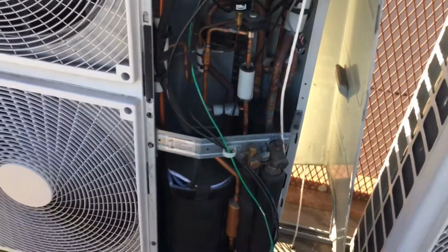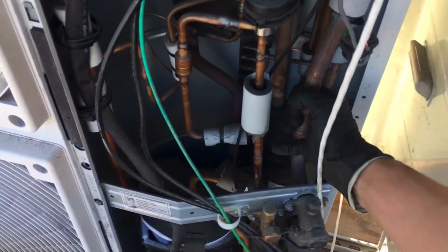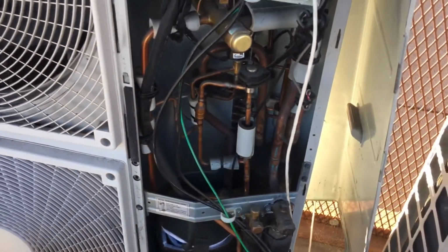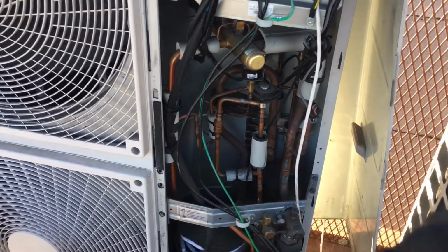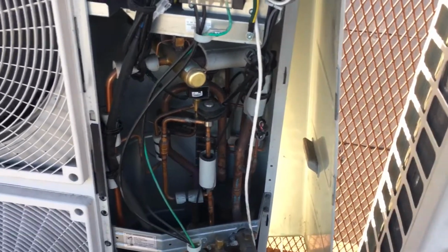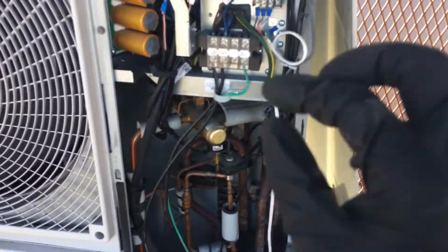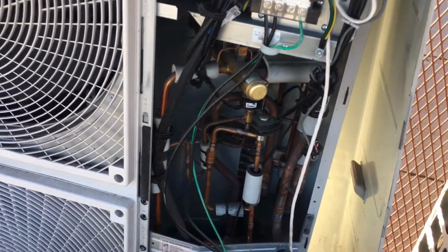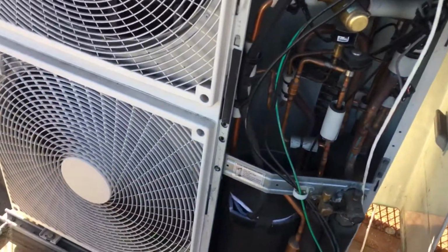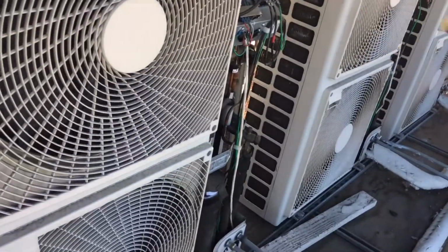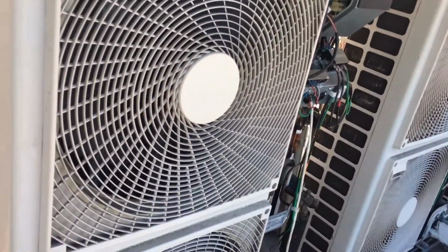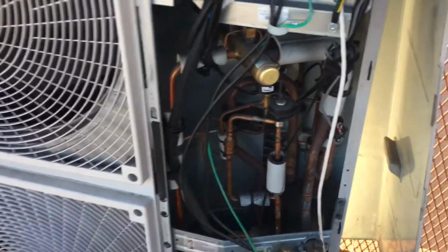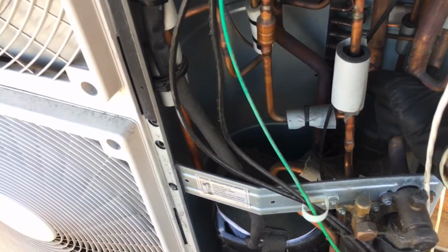I haven't even walked in the building, I just came directly up here, and I'm gonna have to do some further tests. I'm gonna go down into the building and look at the heads and look at the filters. I know they clean the filters. They're very good now at cleaning their filters. They clean their coils. They know about cleaning, because these are all, and this one here is wall mount units, and I told them not to get wall mount units, but they went with wall mount units. All my other ones I installed, he listened to me, we got the more commercial high static pressure ducts in all the rooms. But unfortunately, I think this one he went with 4 wall mount units, and usually you have problems with wall mount units. But I'm gonna go check them, see how everything is.